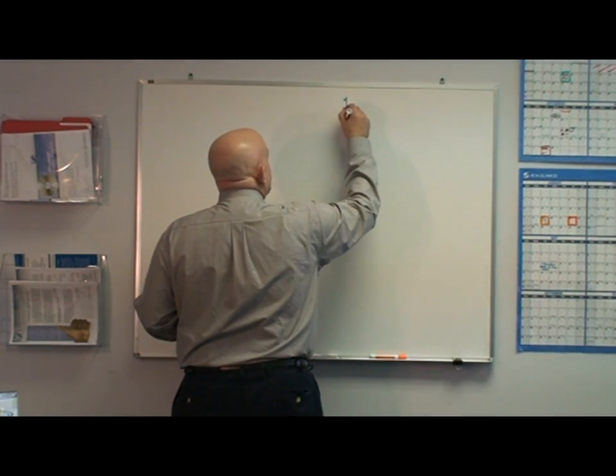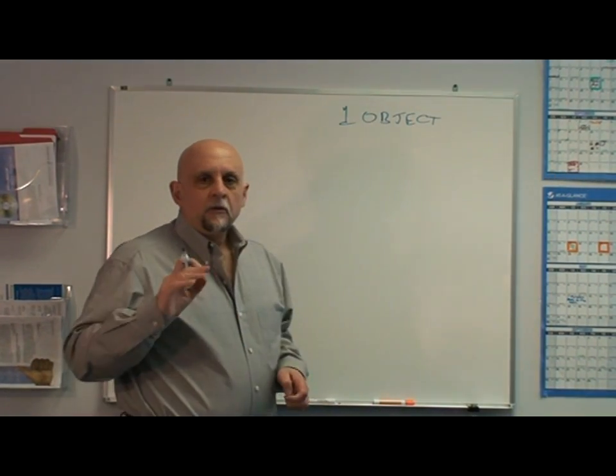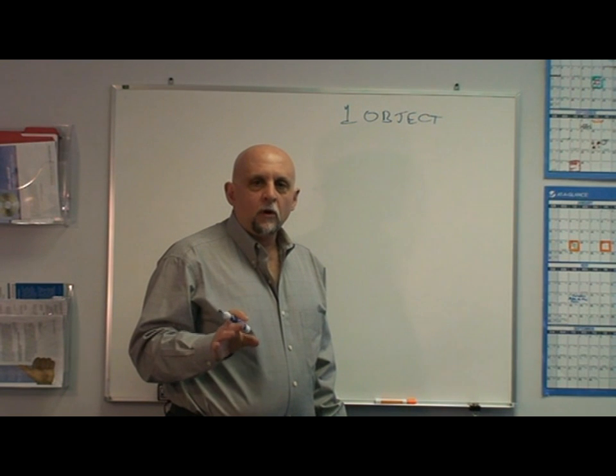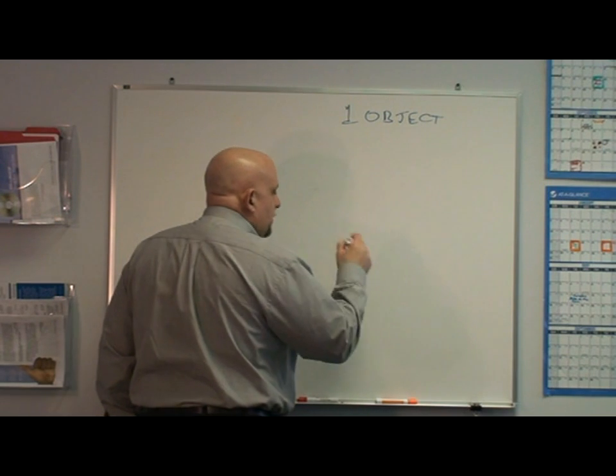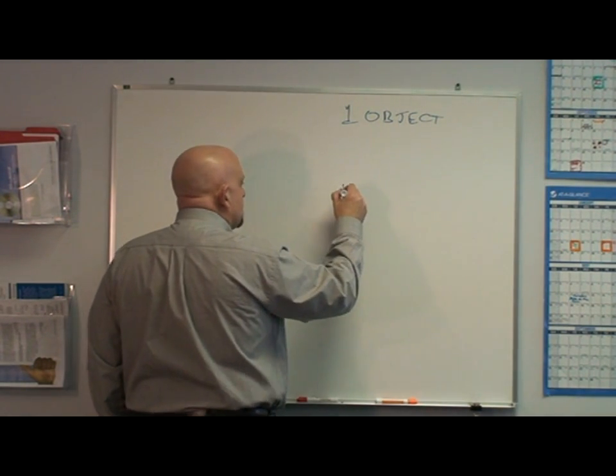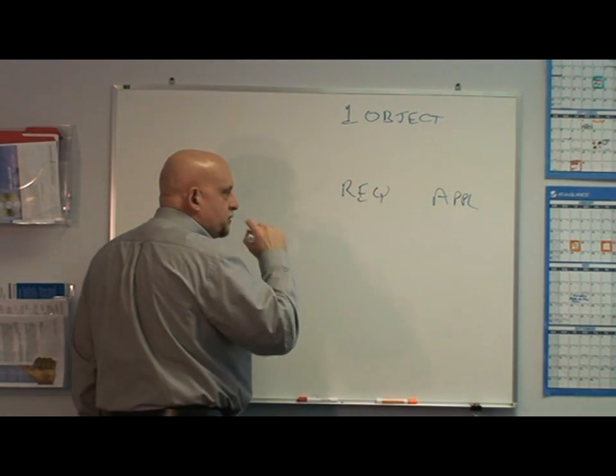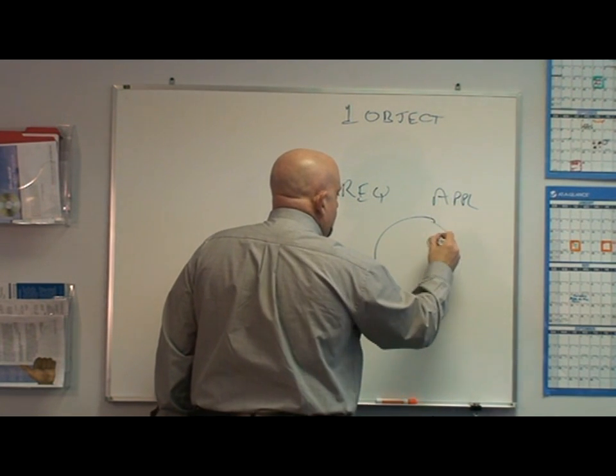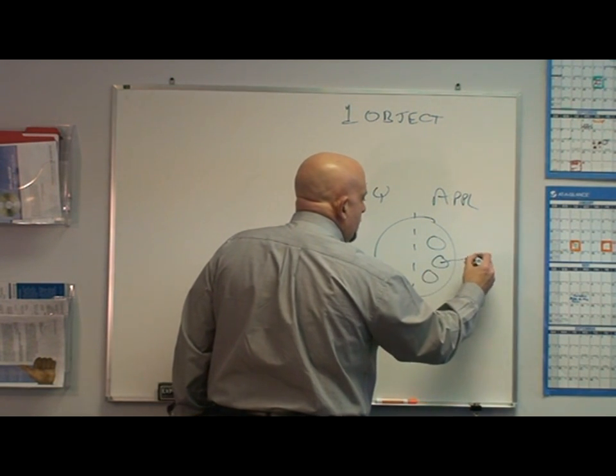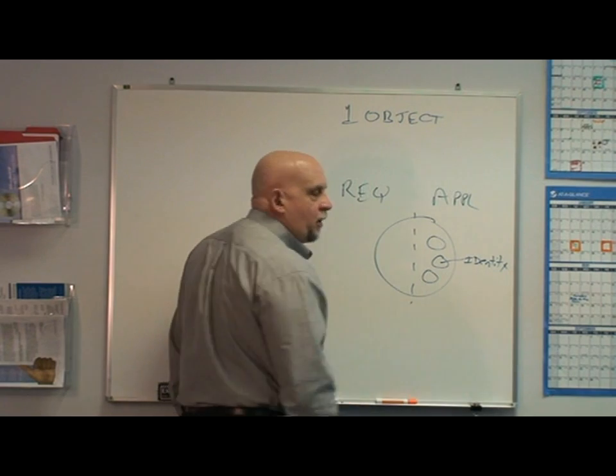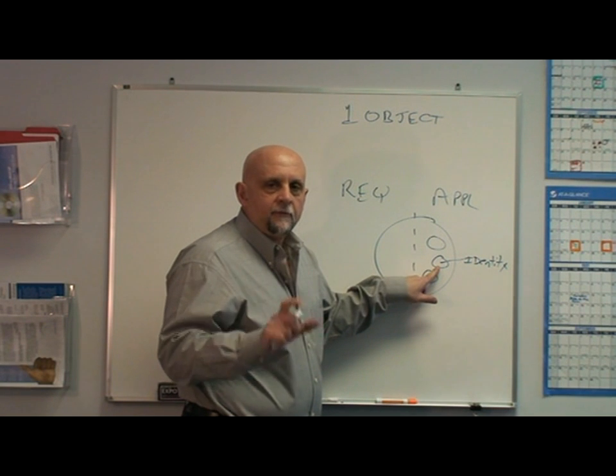Number one, you need to know that DeviceNet is object-based. That means the external view of every device on a DeviceNet network looks like a set of objects. There are two kinds of objects: there are required objects and there are application objects. The identity object would be one of the prime objects that you find in every device — it's simply a collection of like data.